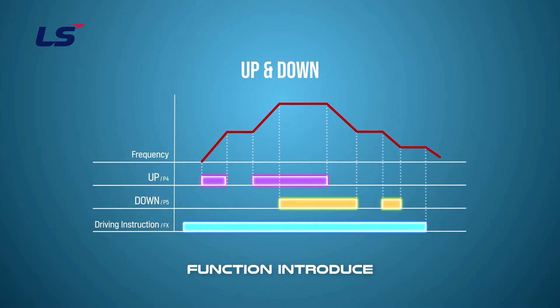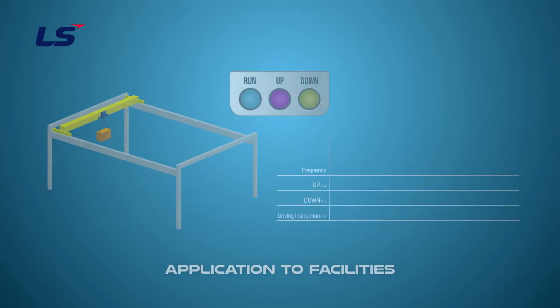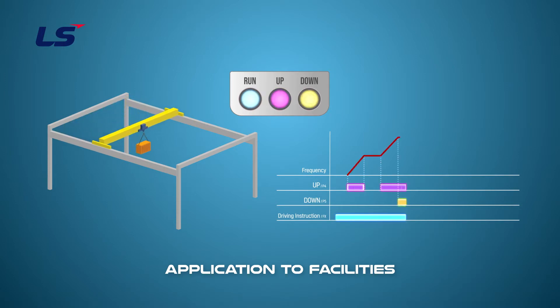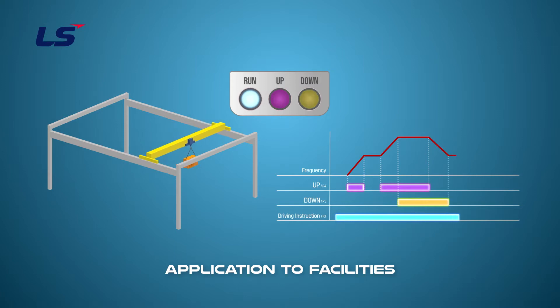If Up and Down inputs are on at the same time, the drive will run at a constant speed. The Up-Down operation can be applied to systems that operate by accelerating or decelerating with a switch, such as an overhead crane.